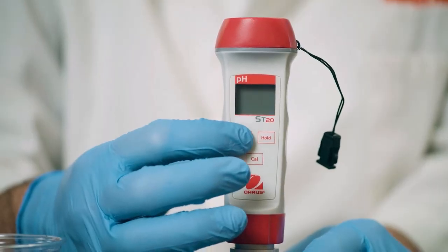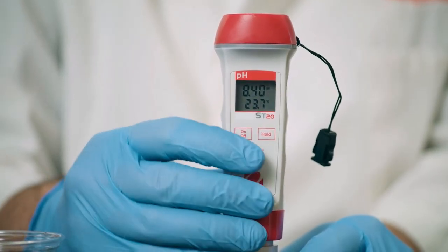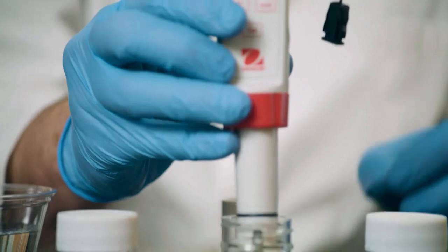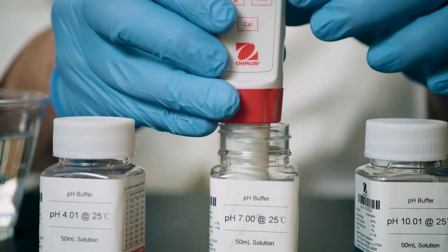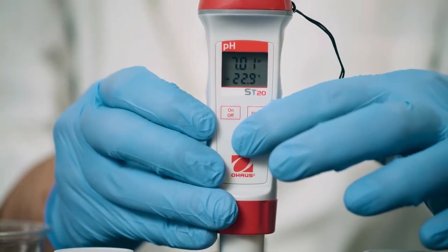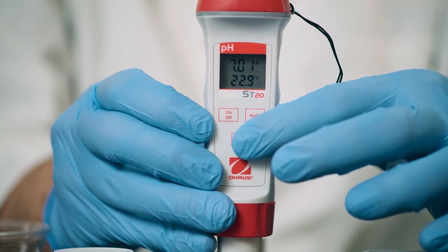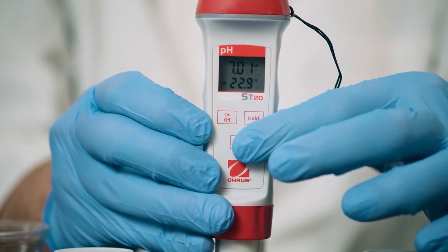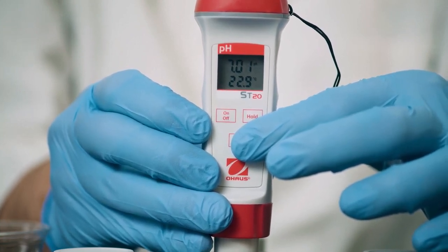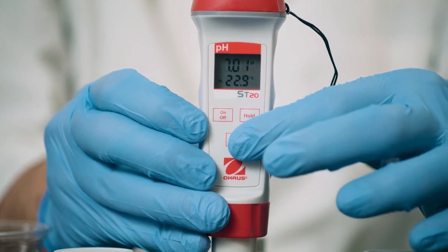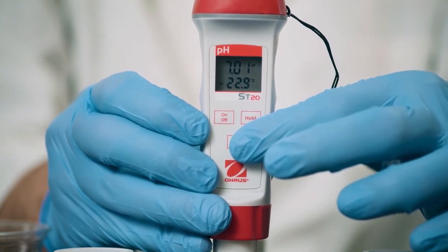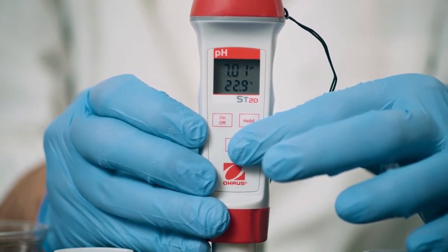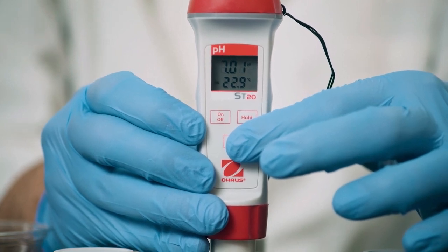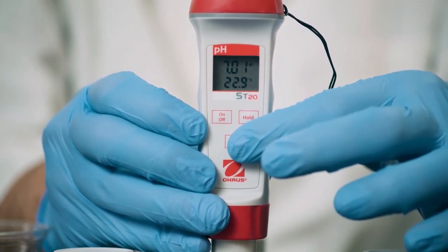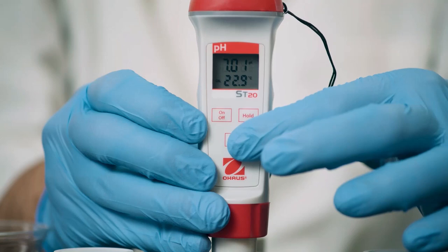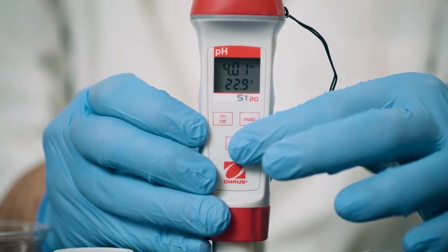Press the on-off button to turn the pen on. Dip the electrode into a pH 7.0 buffer. Press the Cal button to enter calibration mode. The pH will be shown with Cal blinking. Due to the automatic temperature compensation, the pH of the buffer shows at 7.01 because the temperature was 22.9 degrees Celsius. The meter will judge if the signal is stable automatically, and once stable, the meter will change to display a value of approximately 4.01, the next buffer for use.